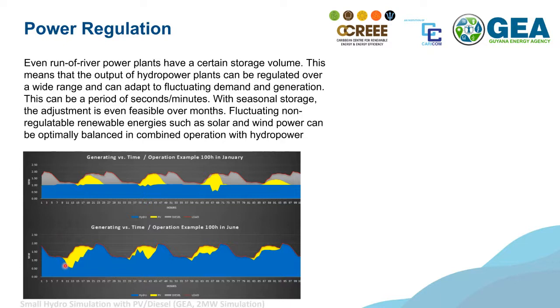At the start of the day, PV is penetrating into the grid, and the hydropower balances by reducing its power to make space for the PV. The whole PV generated over this day could be integrated while the hydropower reduced output. This hydropower has a small reservoir, so it could store water for some hours and feed it out at night. In this example, only hydro and PV are working together because the hydro is strong enough and has enough power at this time.